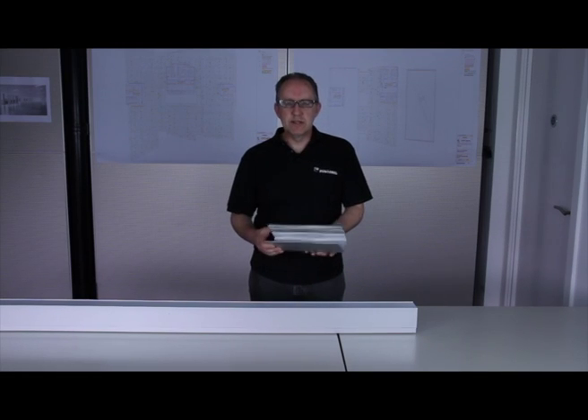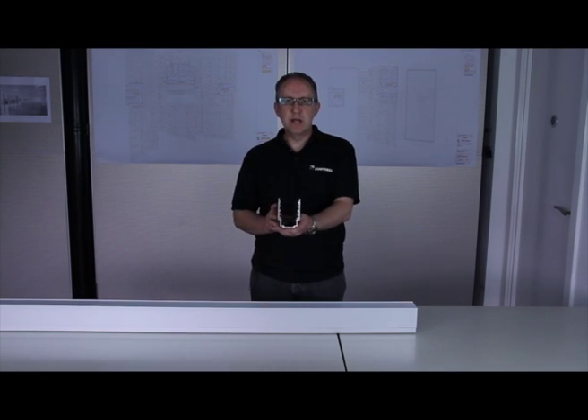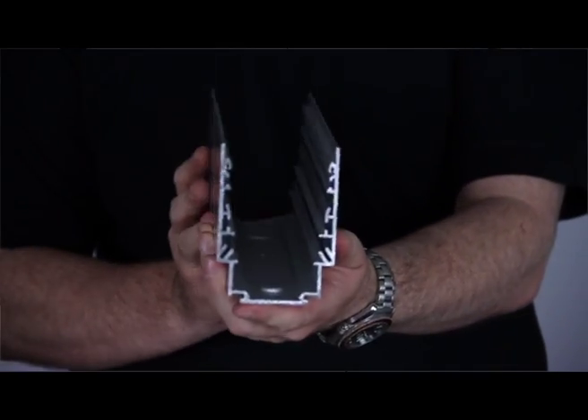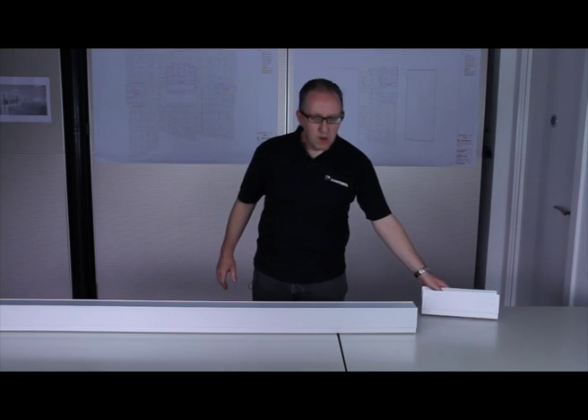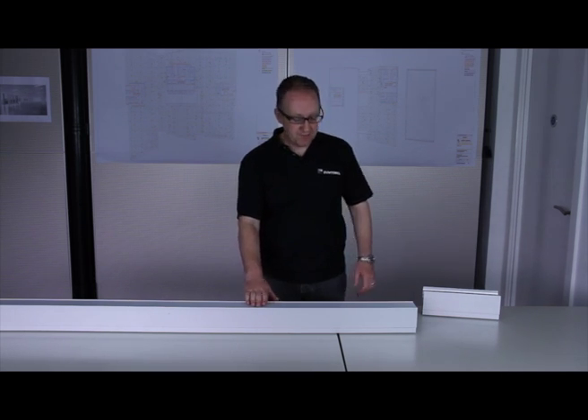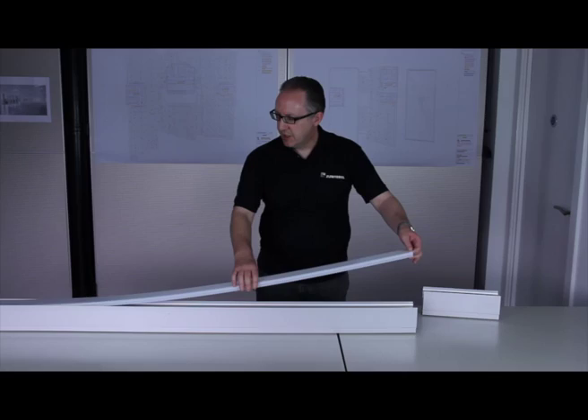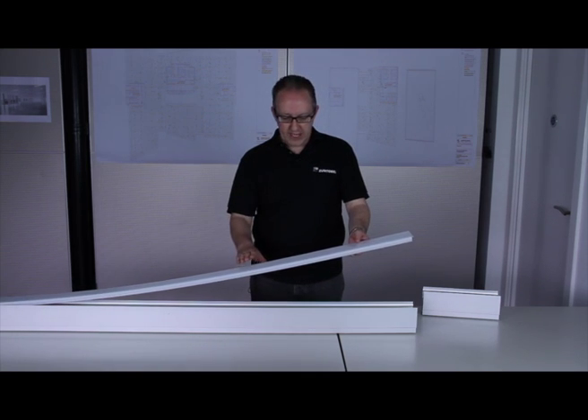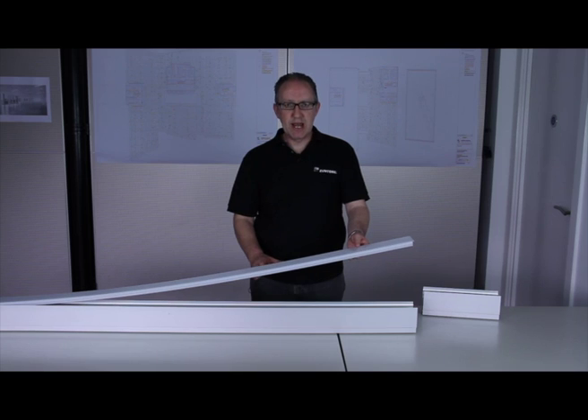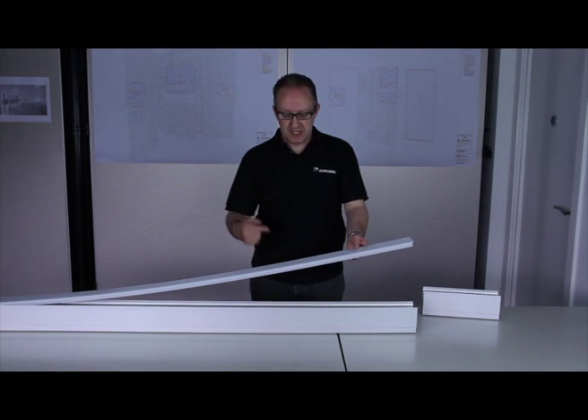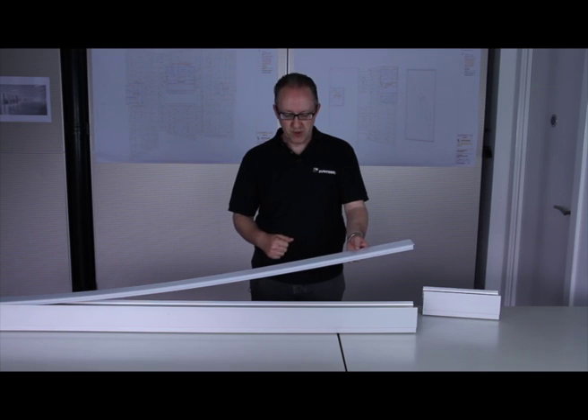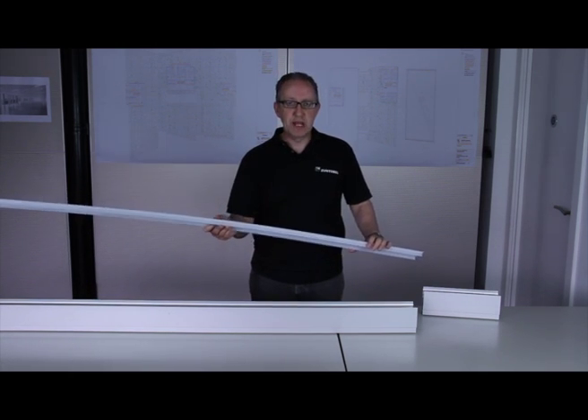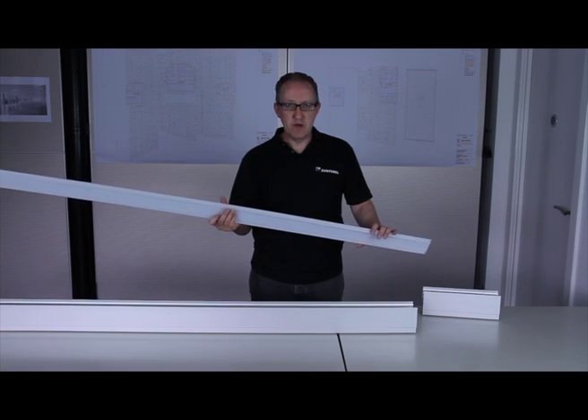The main component of slot light is the extruded aluminum profile. When this profile is delivered to site, it will be delivered complete with the diffuser. The diffuser should be marked to show exactly which piece of extrusion it came from because it will need to be fitted back into exactly the correct piece of extrusion, and then it should be removed and stored safely in a clean area.